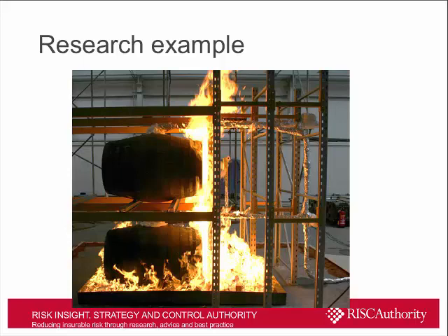This research program was a bit of an eye-opener because the scenario it related to, here we have a two-tier racking system shown, but actually the real scenario was much higher than that. So it's a big consequence scenario, and the research found that actually there was only a few seconds difference between the steel reaching this critical temperature and the first head's opening. So we often hear criticisms that sprinkler system design is hugely wasteful in terms of safety margin built in, but actually we found that in this scenario that was not the case at all.